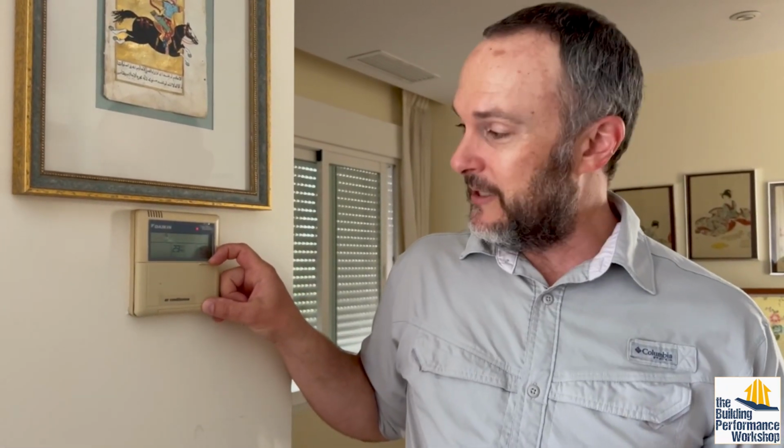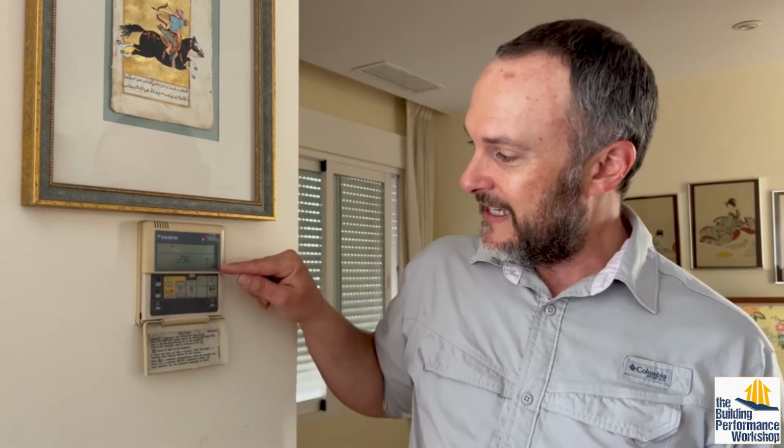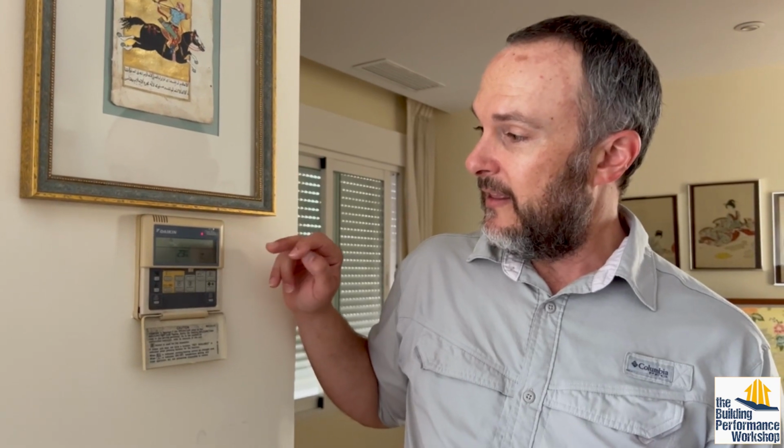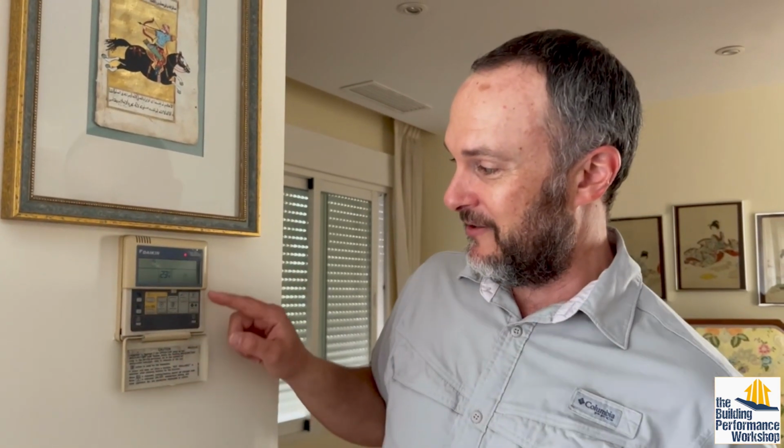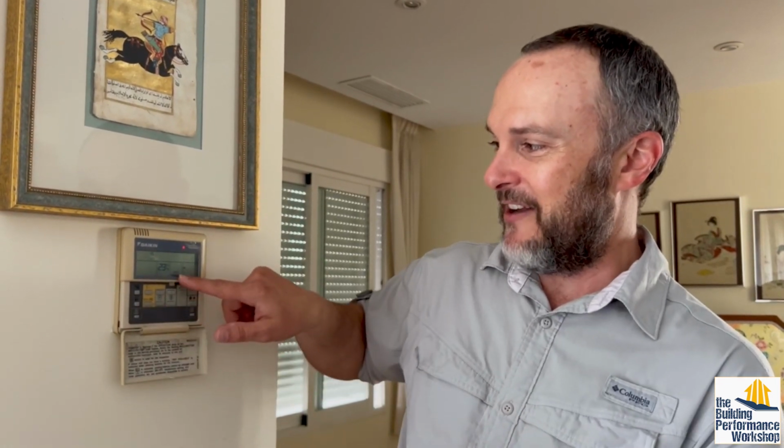Now, the one last thing that I would say is, in the settings here, this is set up to run fan continuously. And since the sewer gas smell is associated with the fan running, this might be a perfect situation for us, since we're not getting any benefit from the filters installed on that thing, to just run in auto mode. So only run the fan when we need cooling. But actually, that's been disabled on this unit. You can't do that. So it has to be specifically configured. It says not available. So unfortunately, we can't do that. So we have to have it run nonstop, which means we're going to have that smell.